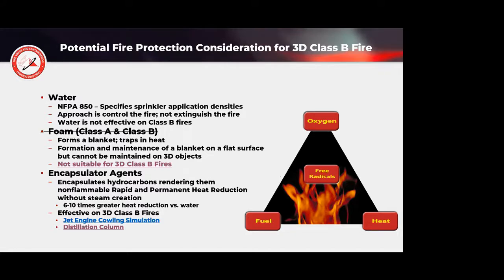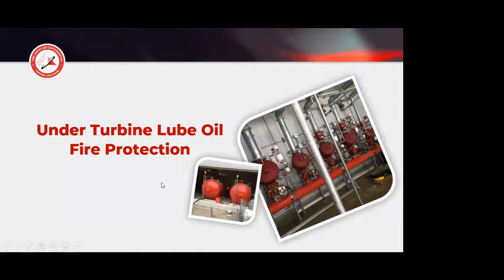then we'd come back and we would spray foam on it, which again surprises me because the dry powder, I understand, is going to try to knock the fire out, but why are you now putting foam on top of something that's like a wall? It's a vertical surface. It's not a flat horizontal surface because the foam's just going to fall down. And if you're trying to cool, why do you want to put a blanket? It's going to trap in the heat. When they've seen some of our stuff, they go, wow, that's very interesting, it's how fast it works. The biggest issue we have is getting the standards to catch up with the agent.